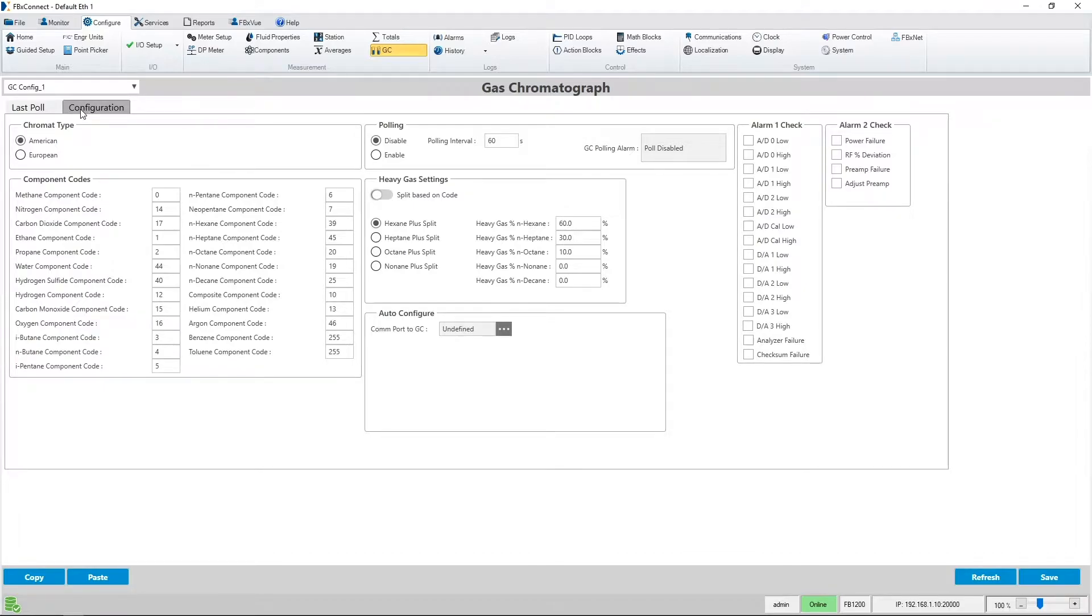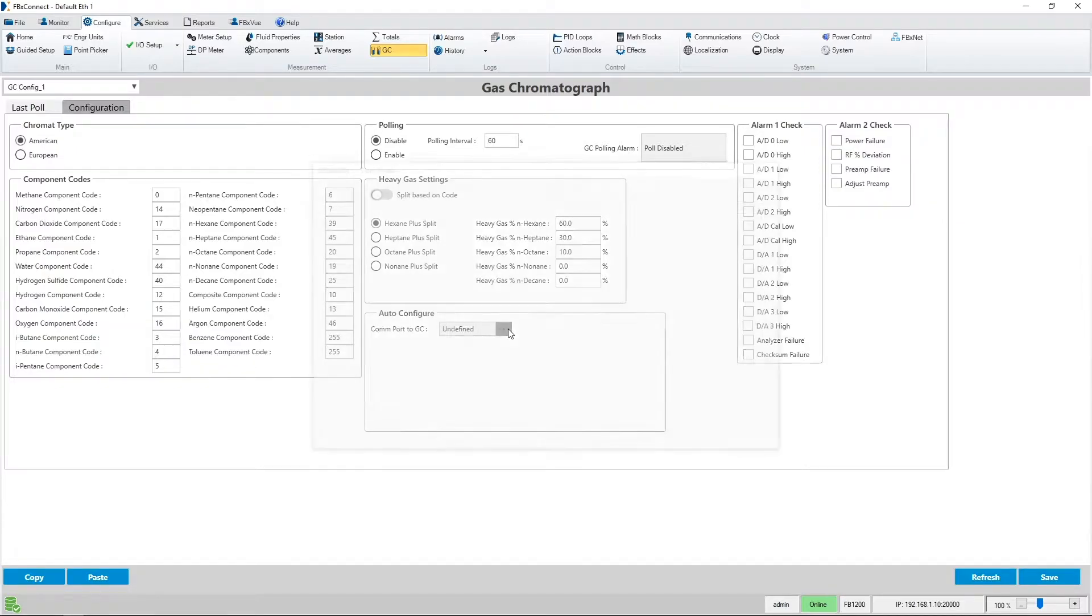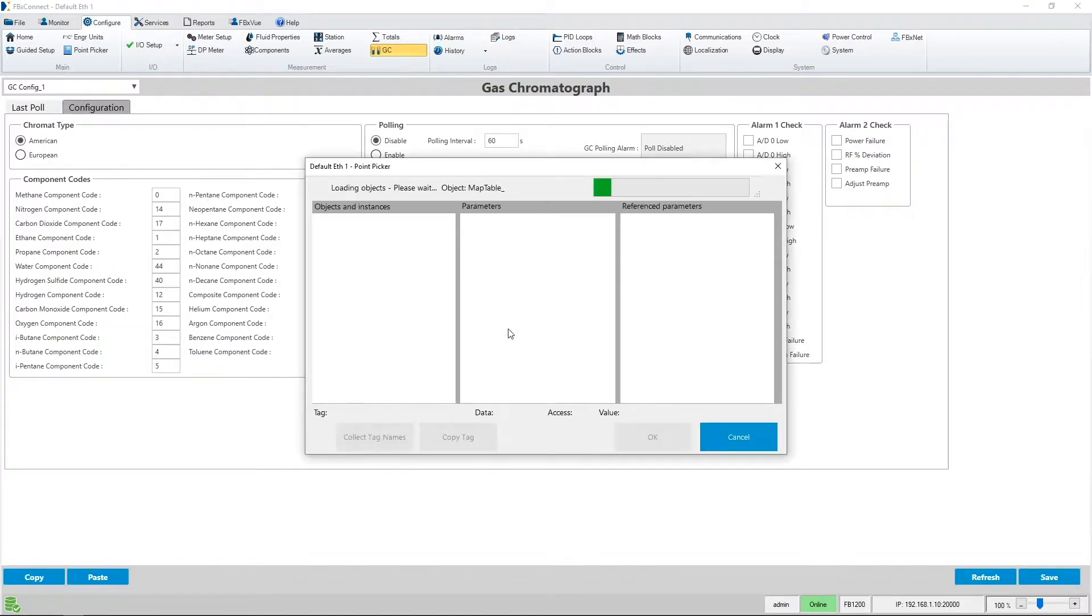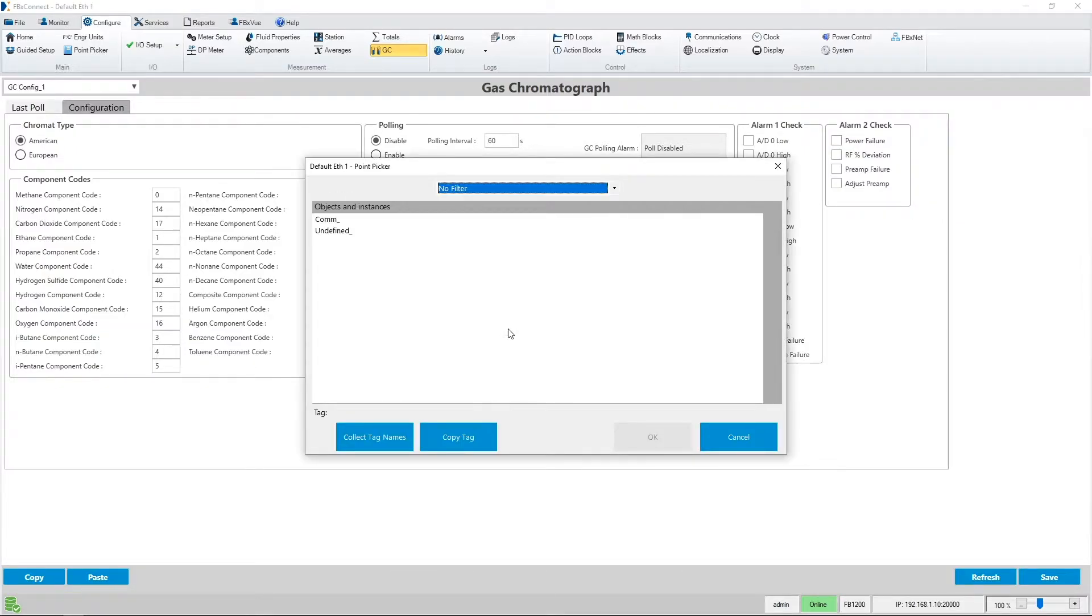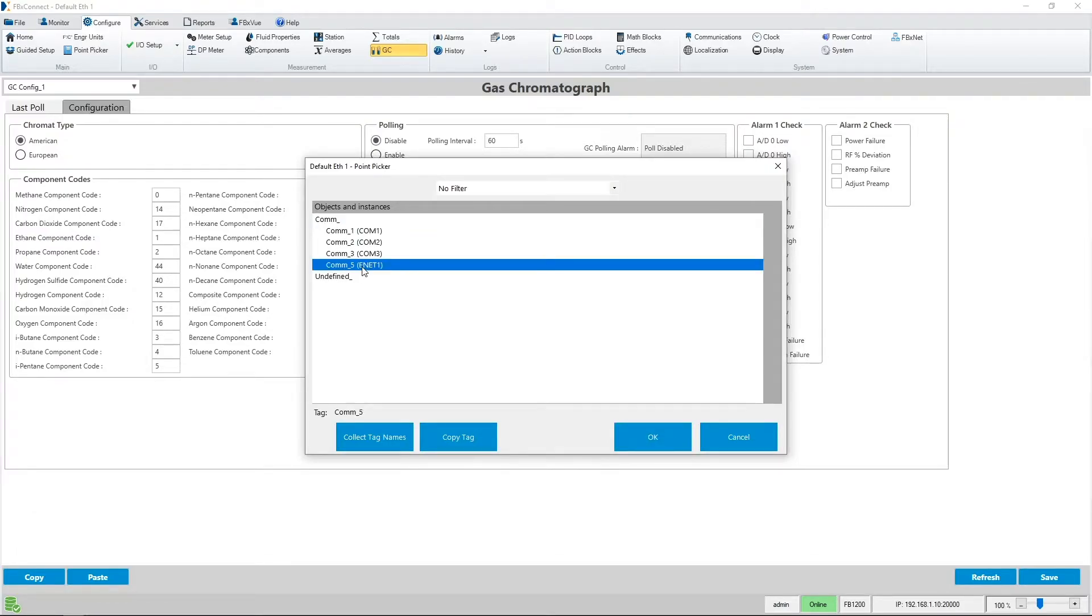The first step is to choose which of the communication ports on the FB Series Flow Computer or FB3000 RTU we'll be using to talk to the GC. In the auto configure area of the display you can open up the point picker to select the appropriate port. For today's example I will pick the Ethernet port which on the FB1200 is COM port number five.